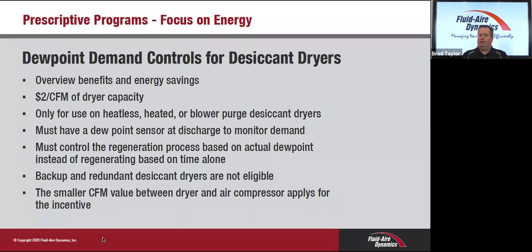Where you require it, you require it. You have to have that low dew point, whether that compressed air is going to the outdoors or whether it's being fed into a lab or through some type of hygroscopic material. We've got to get that dew point down. When we're talking about dryers, especially ones beneath 200 CFM, they're really dumb, for lack of better words. The controls are very simplistic in the way the dryer operates.